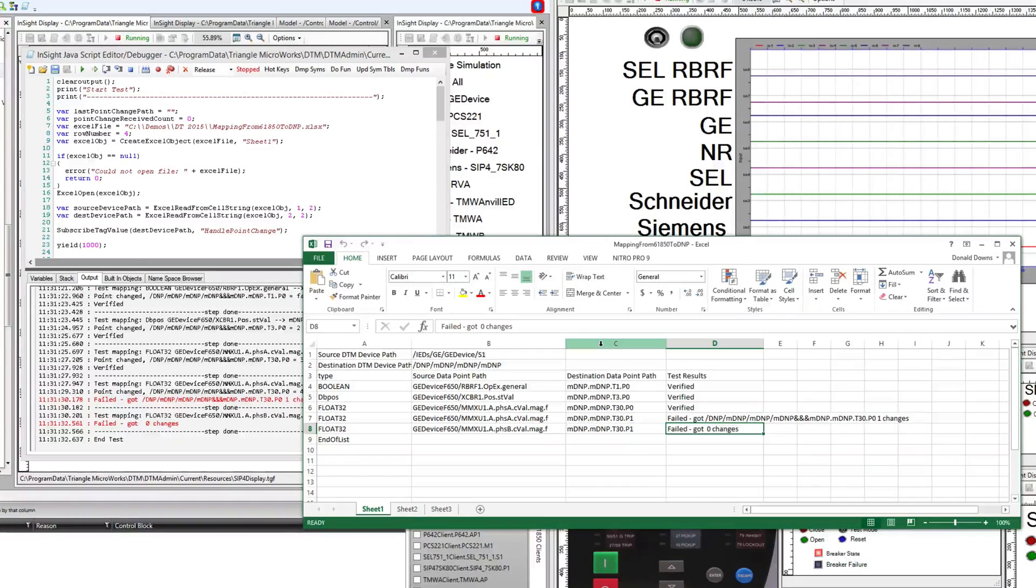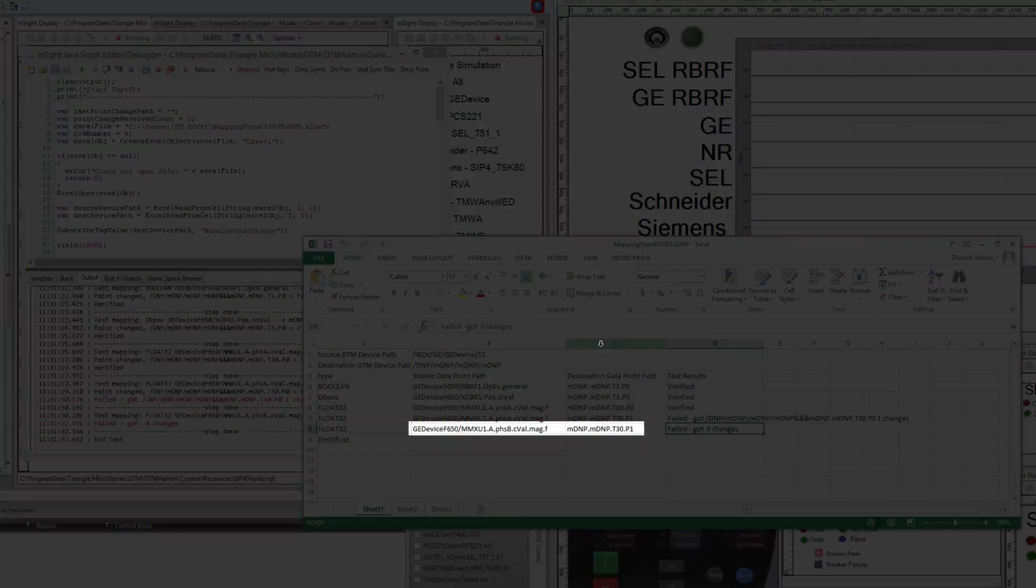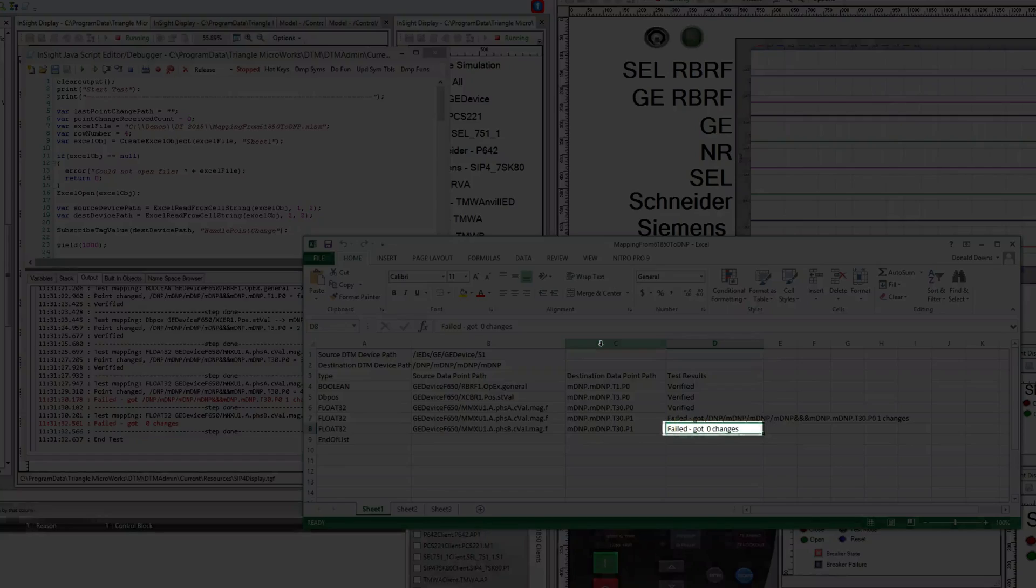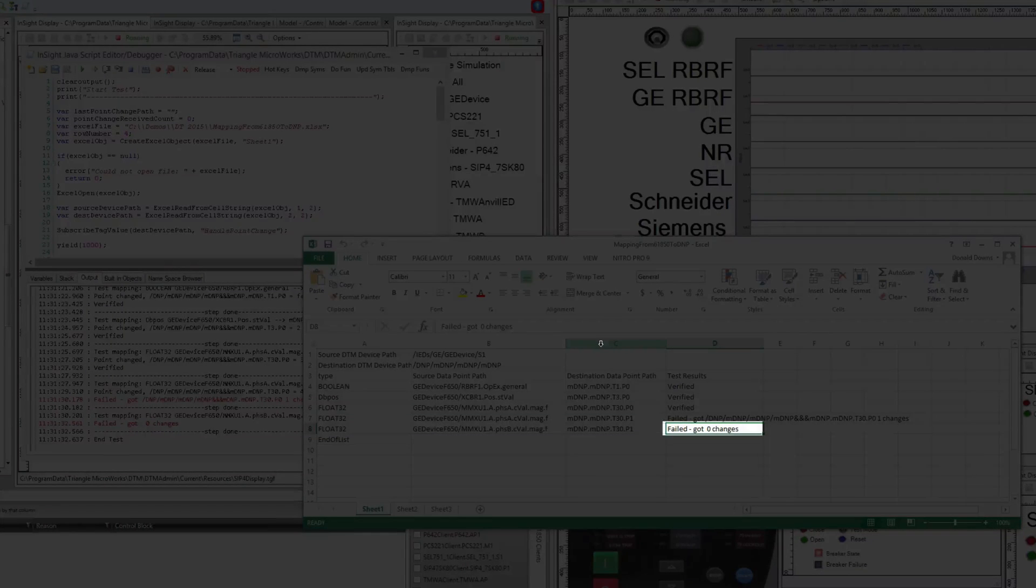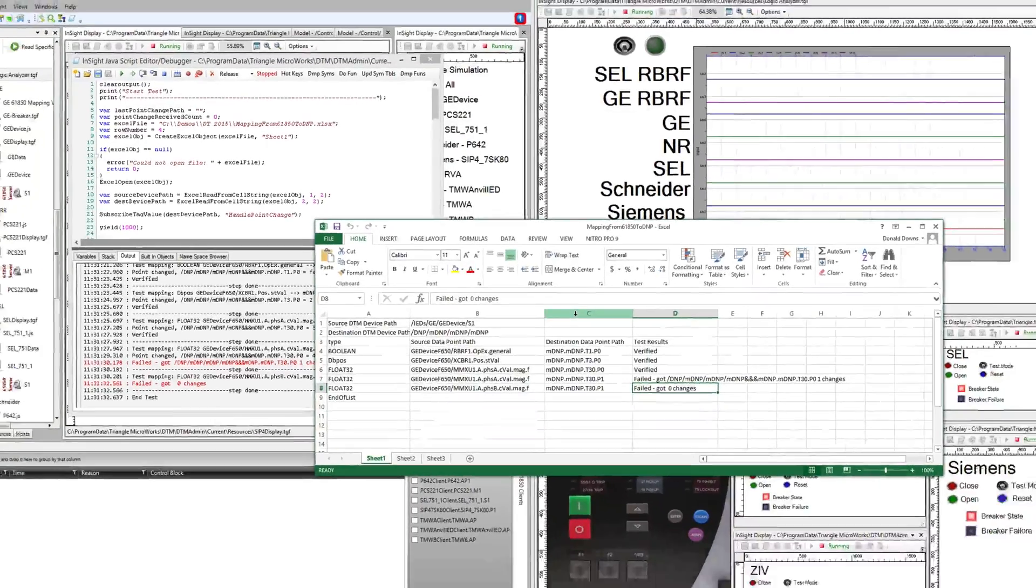The second error shows a missing mapping. The Excel file indicates the phase B current magnitude is mapped to DNP3 analog point one, but changing the current did not affect this point. Additionally, no other points changed, indicating that the phase B current magnitude is not mapped to any DNP3 point.